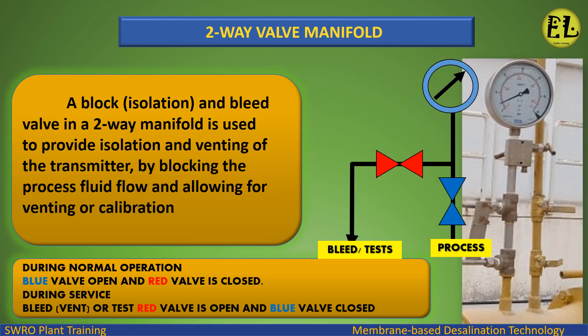A block, isolation, and bleed valve in a two-way manifold is used to provide isolation and venting of the transmitter by blocking the process fluid flow and allowing for venting or calibration. During normal operation, the blue valve is open and the red valve is closed. During service — bleed, vent, or test — the red valve is open and the blue valve is closed.